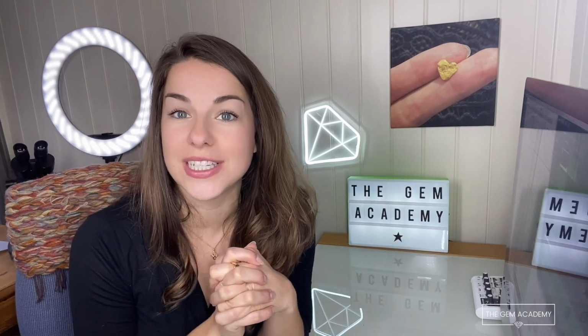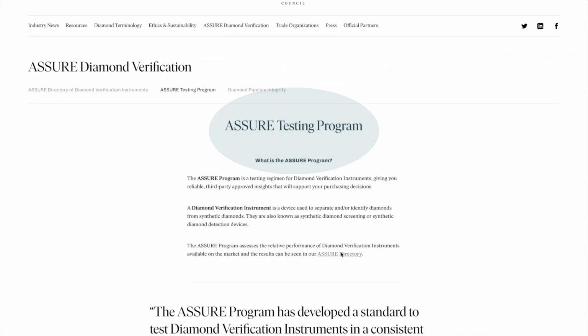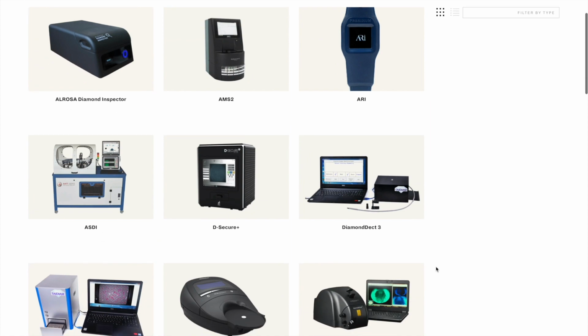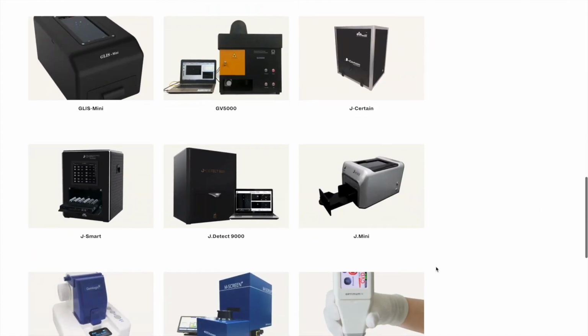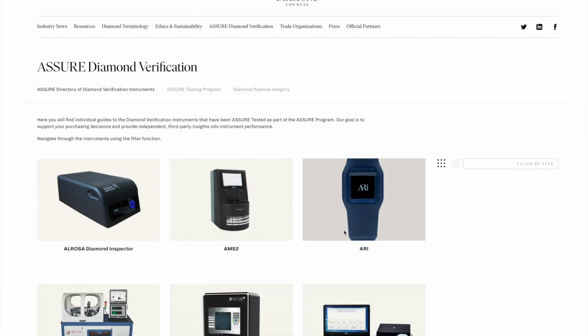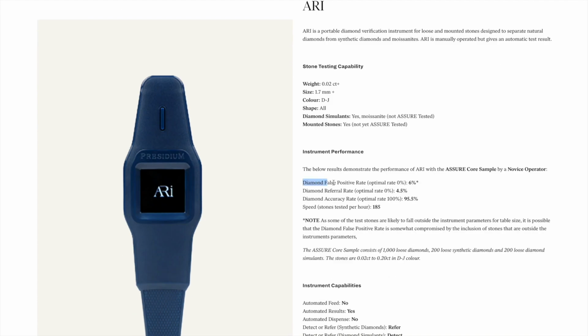To finish off, let's check out the ASSURE testing program and see what they've got to say about the ARi. The ASSURE testing program is run by the Natural Diamond Council, who rigorously test the accuracy of equipment designed for laboratory-grown diamond detection. As you can see, the ARi has a false positive of 6%. This means that 6% of the laboratory-grown diamonds that have been tested under this program gained the result for natural diamonds, so they gained an incorrect result.